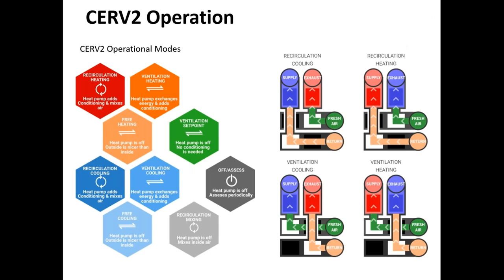The overall operation of the unit is controlled through a reversing valve on the heat pump side to switch between heating and cooling operation. And then there are dampers in the airstream that divert the airflow depending on recirculation versus ventilation configuration. So that's what these schematics are meant to show. On the left side shows all the different modes of operation. You also gain a few modes by having the heat pump on or off, so that you may have just free cooling or free heating operation where you're bringing fresh air in, but energy recovery or heating or cooling are not necessary or needed.